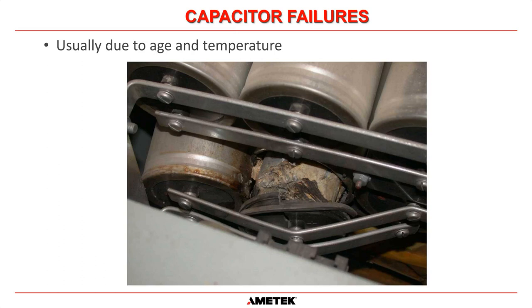Another thing that we see on a regular basis is capacitor failures if the planned maintenance for the UPS is not followed. And capacitors are just like short-term batteries. And batteries are affected by age and temperature. So a capacitor has electrolyte in it, and that electrolyte is in a liquid form, usually inside a capacitor. It's soaked into some form of paper, but that electrolyte eventually will dry out with age and temperature. And when it starts to dry out, it starts to become resistive and will cause the capacitor to heat up. And then that heat will cause the capacitor to expand. And basically, you can see in this picture here, this is what the bus bar should look like. And this capacitor here, there's the lid or the top of the capacitor can. You can see that it's completely burst out and bent that bus bar.